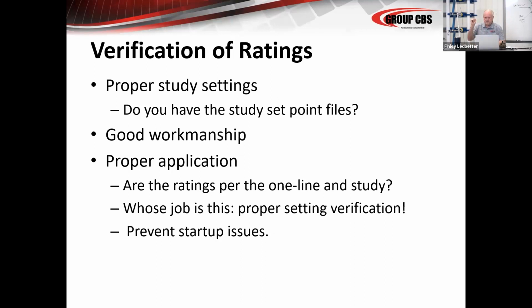And I'm walking to the substation with a flashlight, and I notice that the differential relay scheme, all of the taps are set kind of in a certain manner. And there's, let's say, 369 of them in this substation. The last one I look at, all the taps are straight in a line. Well, being an ex-Multi-Amp guy, I realized that when you test that relay, a BDD or an HU, a BDD, you might set all the taps in one location to test, but then you put them back to the as-left settings before you leave.